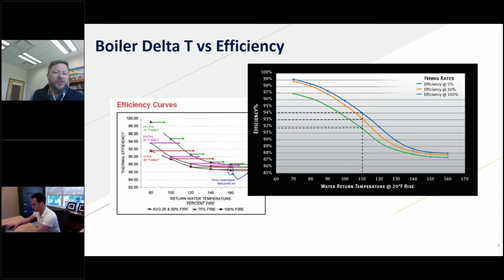The advent of condensing boilers has really driven a lot of that, as has the advent of heat recovery chillers and the ability to provide warmer and warmer water temperatures. And so from a terminal device or a distribution system, we can handle lower hot water temperatures, and we've got equipment that's optimized to deliver those lower hot water temperatures, and you end up with a more efficient system.